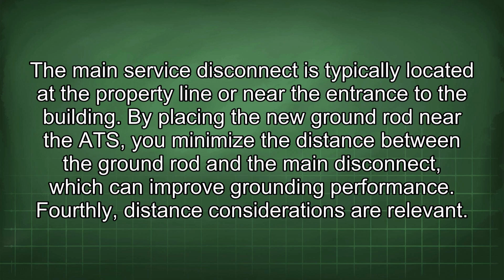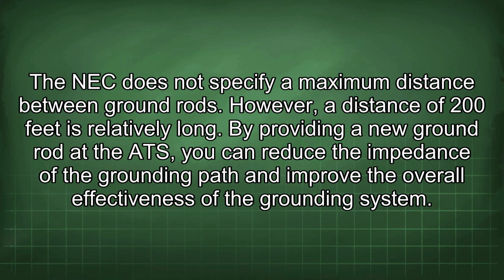Fourthly, distance considerations are relevant. The NEC does not specify a maximum distance between ground rods. However, a distance of 200 feet is relatively long. By providing a new ground rod at the ATS, you can reduce the impedance of the grounding path and improve the overall effectiveness of the grounding system.